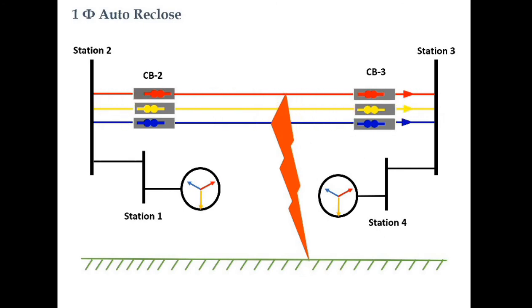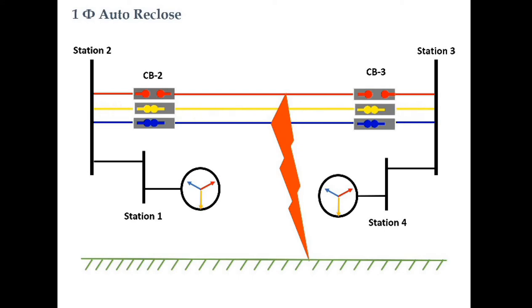Because of the fault, the relay at Station 2 and Station 3 will sense the fault and give an opening command to the respective circuit breakers — Circuit Breaker 2 and Circuit Breaker 3. From the figure it can be observed that all phases have different compartments, meaning these circuit breakers are single-pole operated. As a result, the R-phase pole in both stations will open. After opening of the R-pole, the fault will be cleared, and the relay at both ends will give a reclose command to the circuit breakers, which will close after one second — known as dead time.